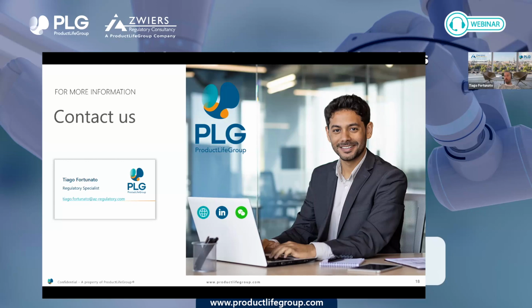Well, to be honest, we have been successful in many situations with different notified bodies, as well as the FDA, just with a qualitative approach for the benefit risk analysis. And like I said, it's the easiest way, as you don't need really to perform any calculations. Of course, if you have a high-risk class device, then besides, like I said, using a matrix with more levels of distinction, of severity, then you probably need to use a more quantitative approach. That's when you decide for that.